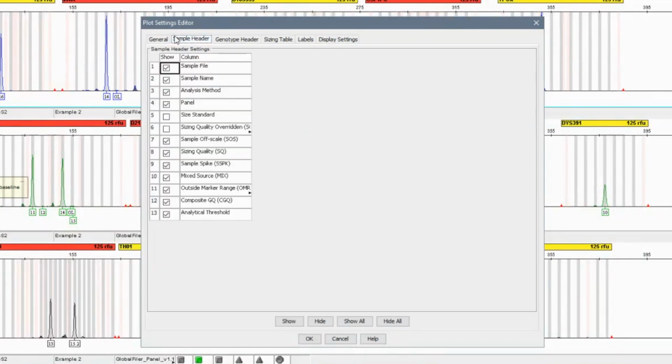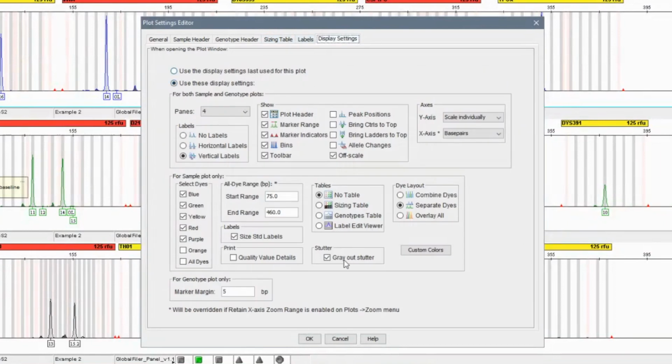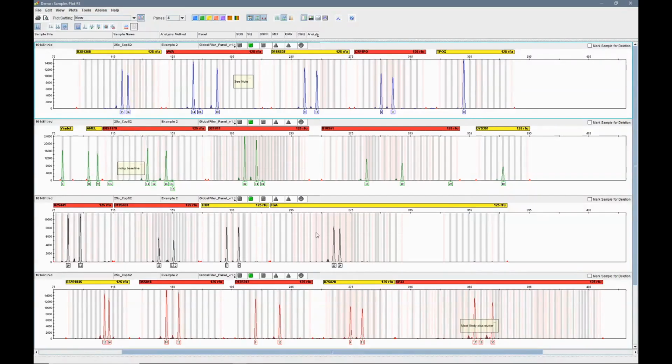You can choose to add that analysis method or panel, as well as the analytical threshold that you're seeing appear in the marker header bars. And then one additional new function we have is the ability to display stutter in a grayed out form.